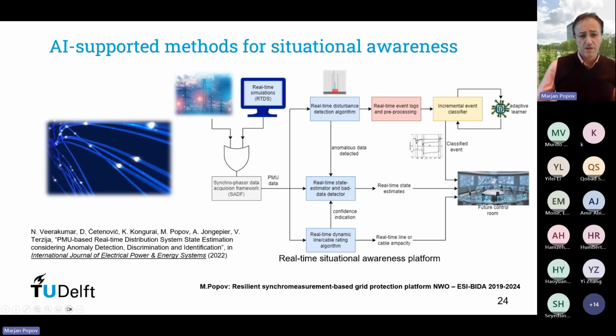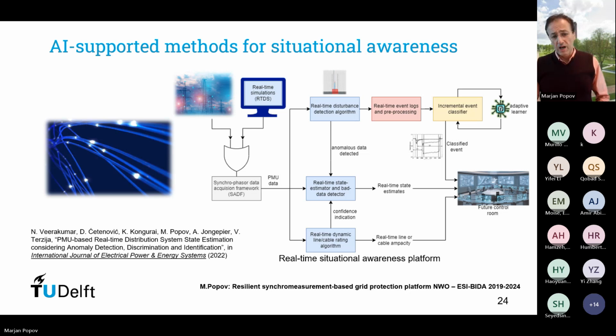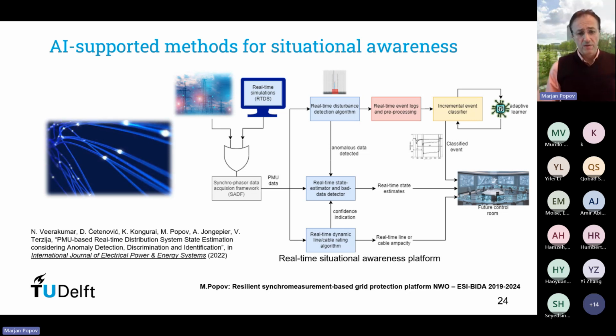Normally, the synchrophasor data, as we could see, we have used to develop a state estimator with a bad data detector, then a real-time disturbance detection algorithm, and finally there could also be other algorithms like, for instance, dynamic line or cable rating. In this case we can determine the cable capacity, or how much reserve we have to load the cable, which is very important to see whether we run the risk of congestion in the network. These other applications can also be a supplement to the state estimator, which determines the system state.